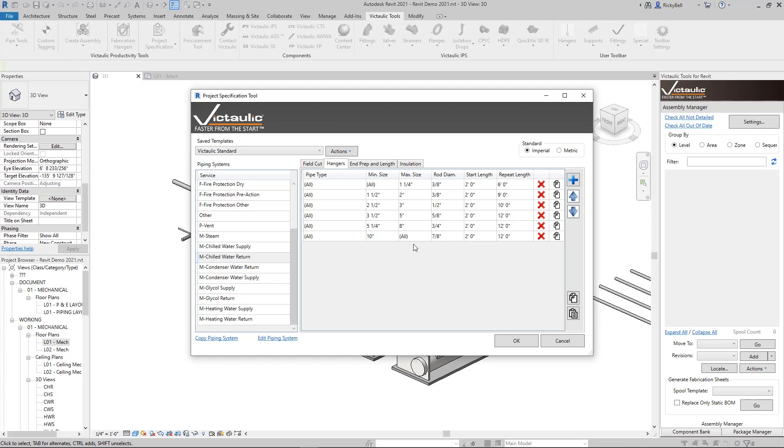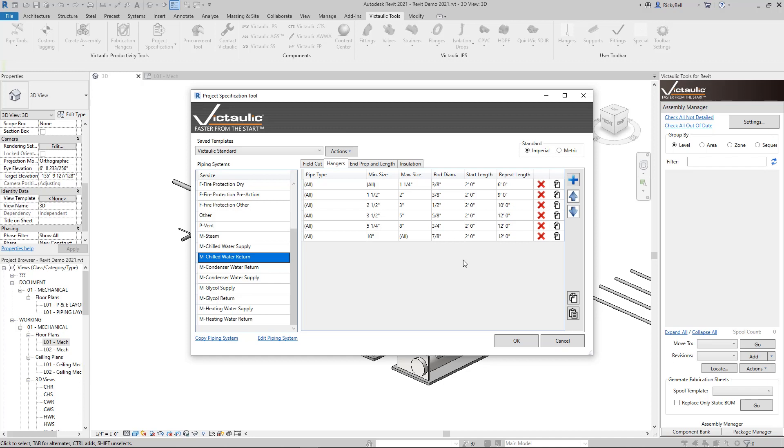These rules that I have set up here, they're very basic, but they're kind of industry standards. As you progress in size for any pipe type, as long as you're in chilled water return in this case, the rod diameter is going to get a little bit thicker every time and the repeat length is going to get a little bit longer every time. So as you're applying hangers later on in the project, you can just trust that the project specification is going to take care of the distances and it's going to be a really big time saver for you.